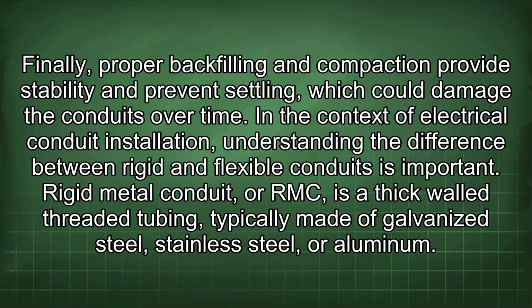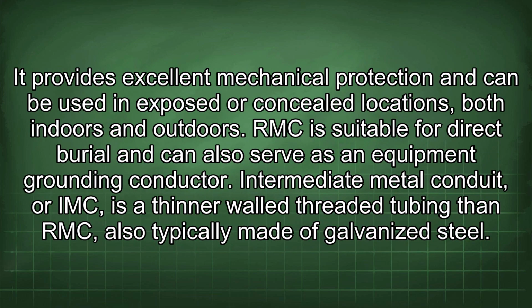In the context of electrical conduit installation, understanding the difference between rigid and flexible conduits is important. Rigid metal conduit, or RMC, is a thick-walled threaded tubing typically made of galvanized steel, stainless steel, or aluminum. It provides excellent mechanical protection and can be used in exposed or concealed locations, both indoors and outdoors. RMC is suitable for direct burial and can also serve as an equipment grounding conductor.